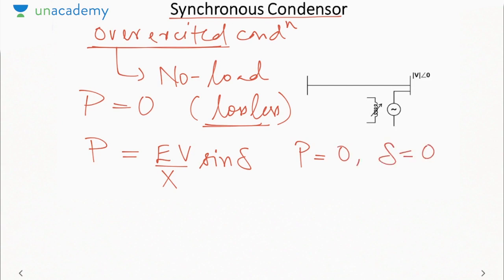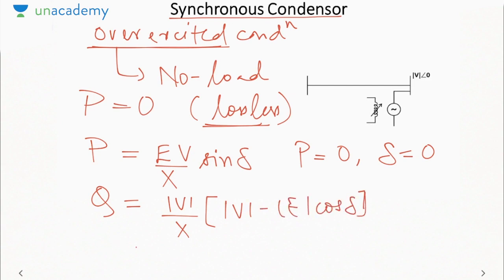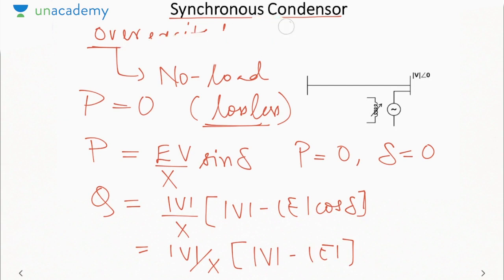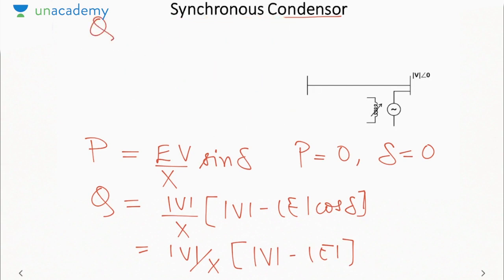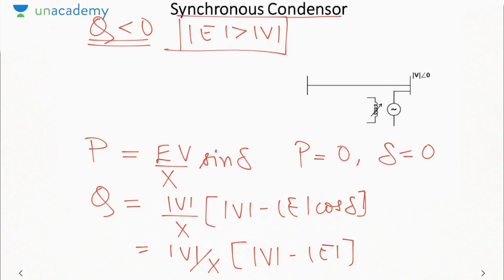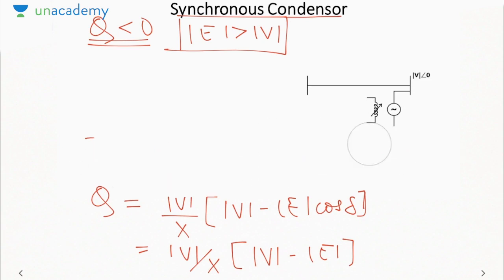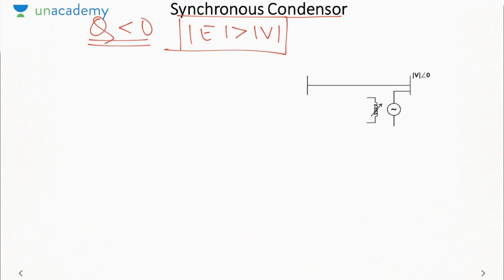If delta is 0, it implies reactive power, which is mod V by X times (mod V minus mod E cos delta), becomes mod V by X times (mod V minus mod E). So for it to work as a capacitor, Q must be less than 0. If Q is less than 0, it means mod E is greater than mod V. So that is the condition of a synchronous condenser or synchronous capacitor, that it must run under overexcited condition. But practically real power is never 0. But if real power is 0, here real power is 0 and Q is negative.